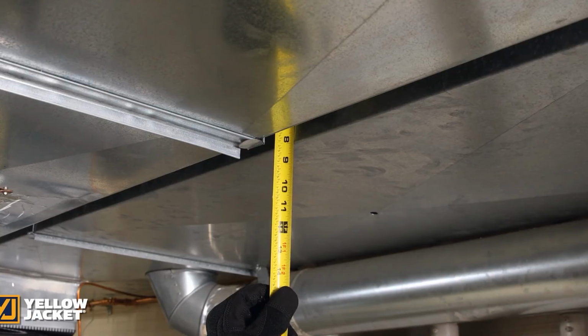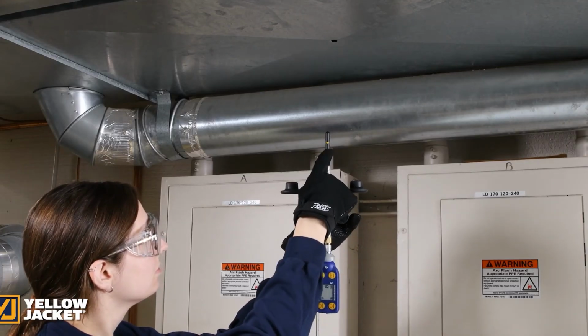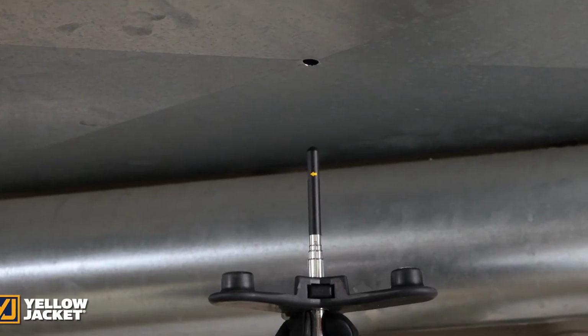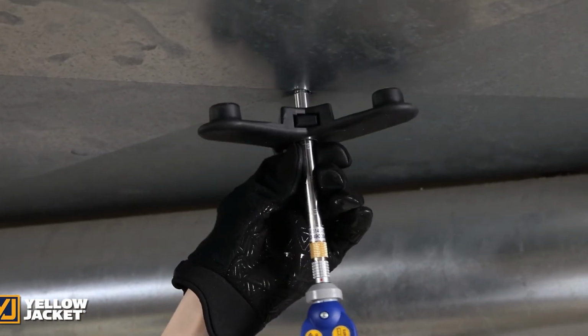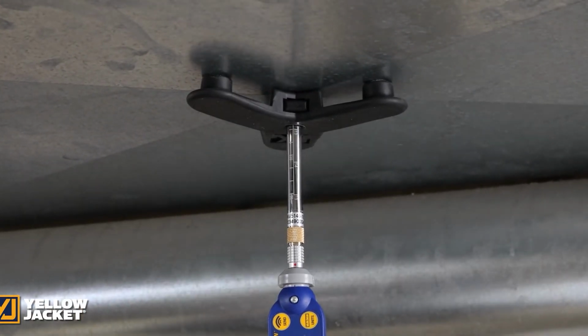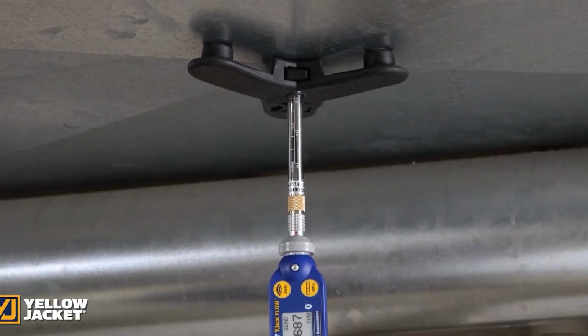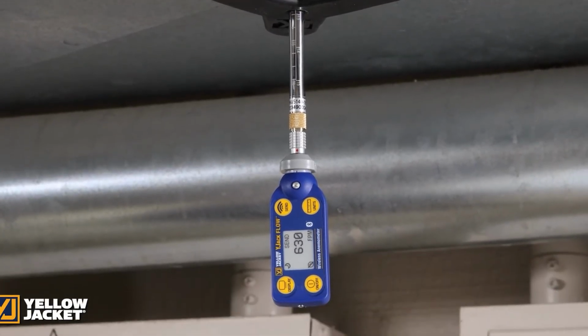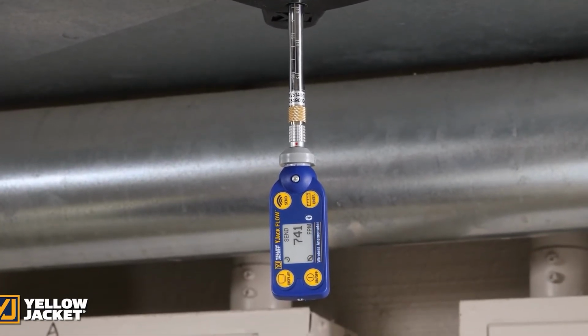In a pre-drilled half-inch hole, insert the probe into the system duct with the arrow pointing in the direction of the airflow. Based on the distance for your first reading called out in the app, the instantaneous linear airspeed will display on the screen.